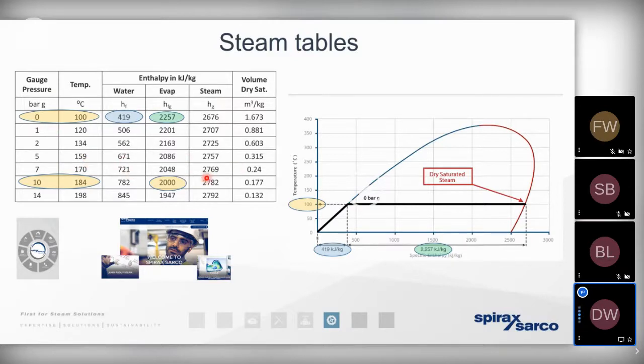But when steam gives up its heat energy and condenses, it's the energy that is demonstrated in this column, the enthalpy of evaporation, the latent heat. That's the energy that is imparted to the process. And what you'll notice is, as we increase the pressure of the steam, yes, there's more energy in the steam, but the useful heat energy, that latent heat, actually reduces. And that's one of the reasons why we want to distribute steam at a high pressure, but consume it at the process at the lowest possible pressure.